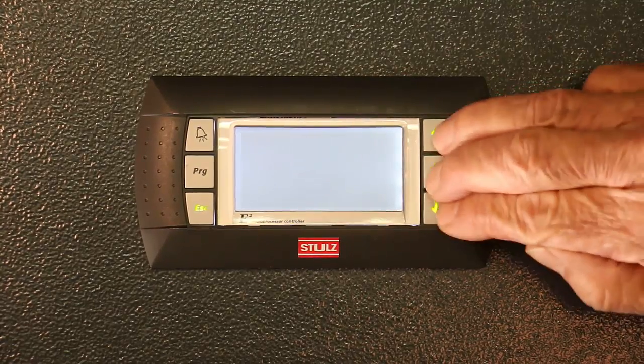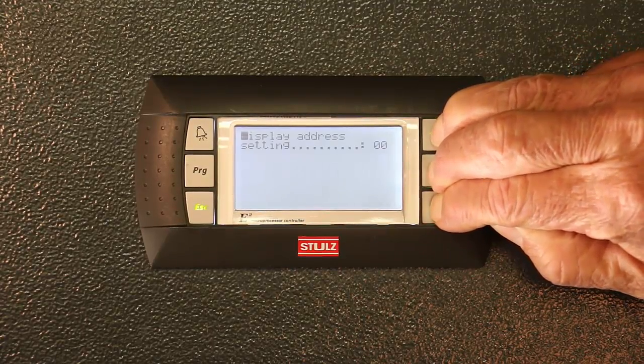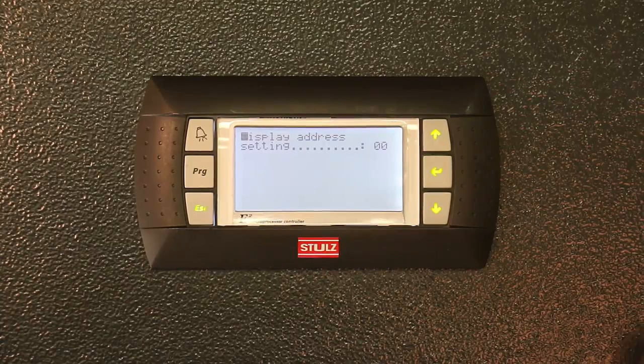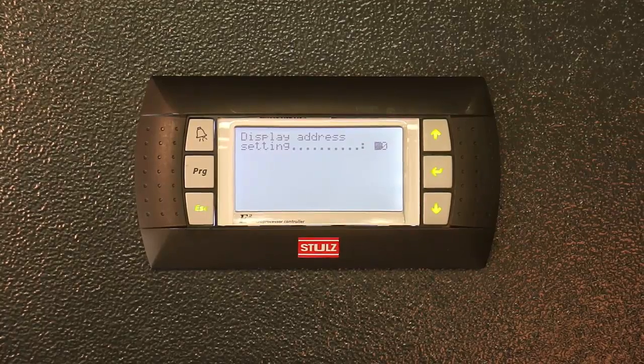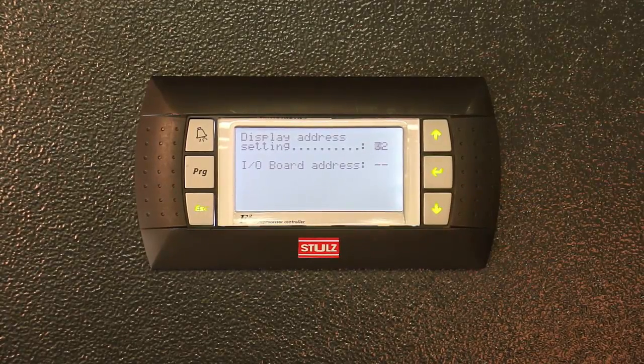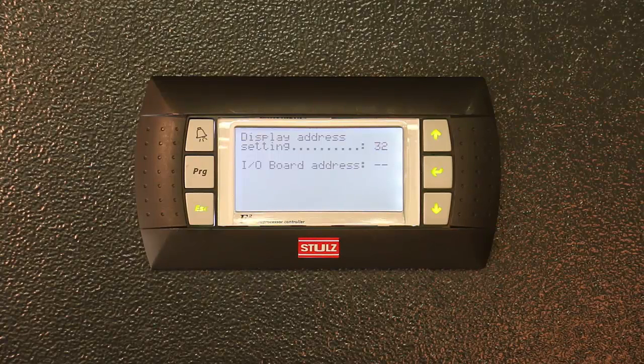Again, we press up, down, and the enter keys together to enter the addressing screen once more. Use your enter key to move the cursor into position. Change the display address to 32 for standalone by pressing the down arrow button. For PLAN grouping, you would enter the desired number for the corresponding unit in the sequence. Note: in a grouping setup, the sum of the I.O. board address and the display address must always equal 33. After entering your desired address number, press enter.